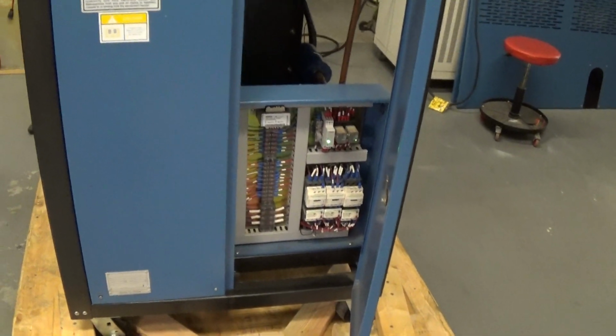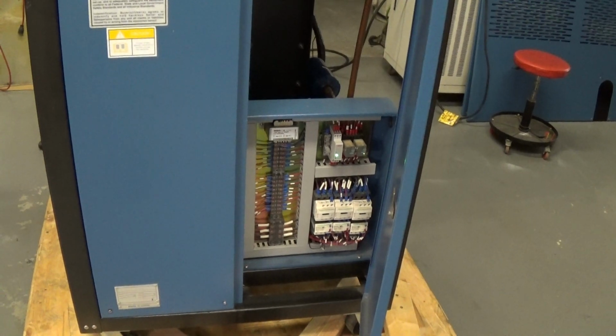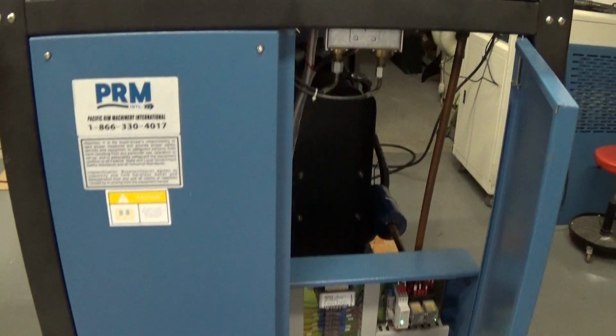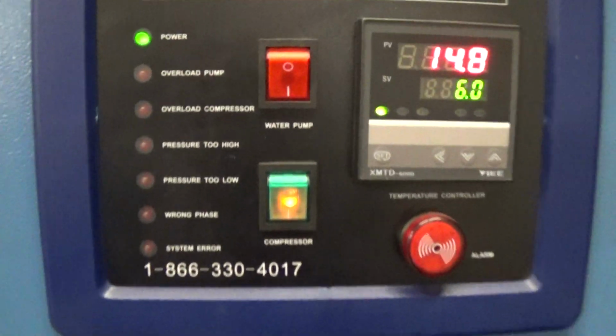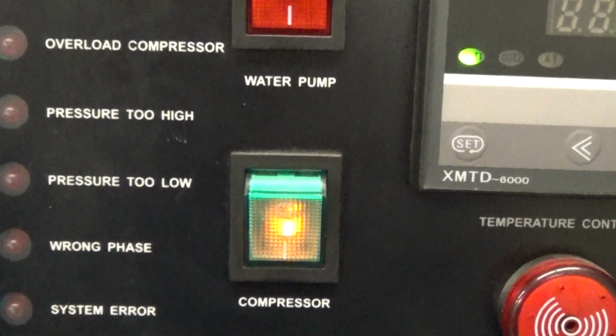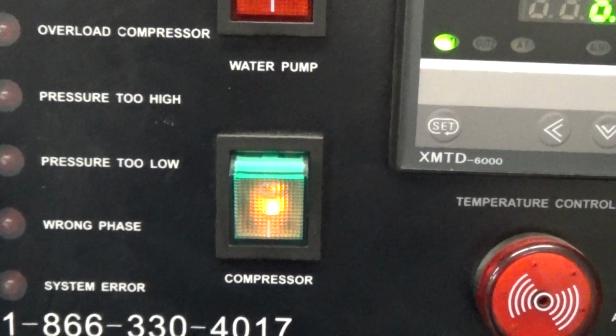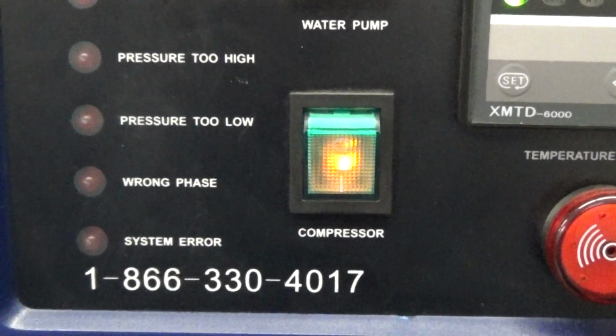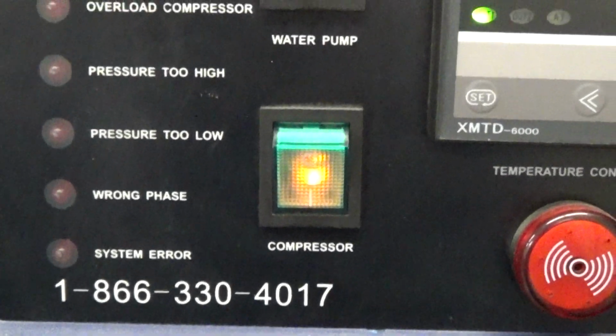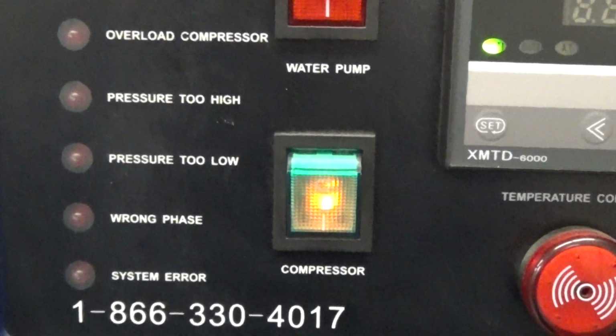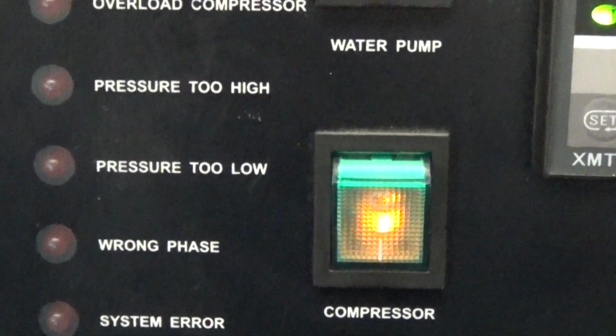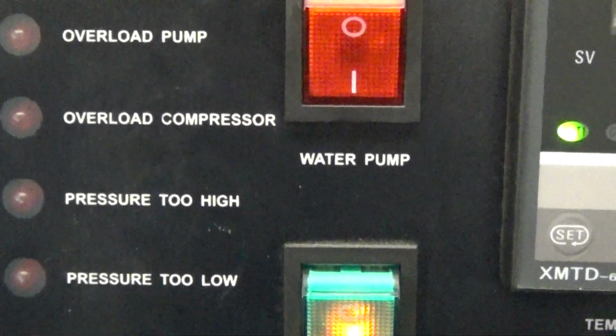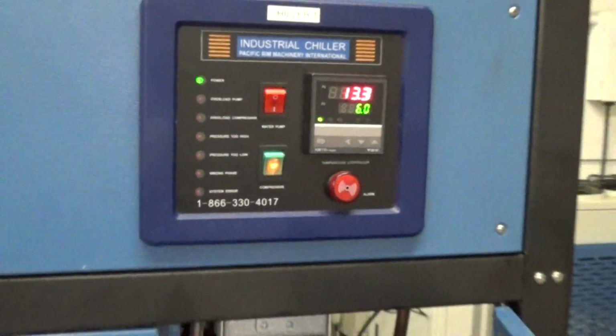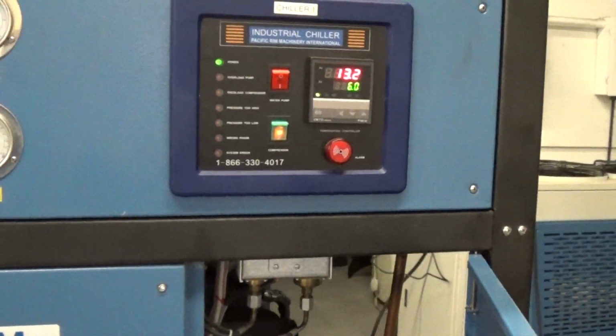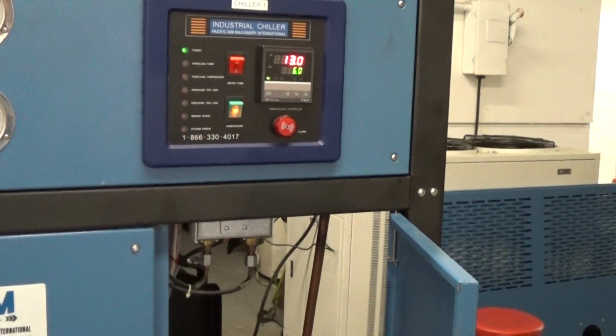This is the proven R407C refrigerant, I think I mentioned. If we do go into low pressure alarm, which is usually due to running too cold a temperature for your fluid, like if you're running 4 or 5C with straight water, you'll get refrigerant pressure too low. And then if you have dirty condenser fans, or you're running in an ambient condition that's way too hot, then you could get a high pressure trip.